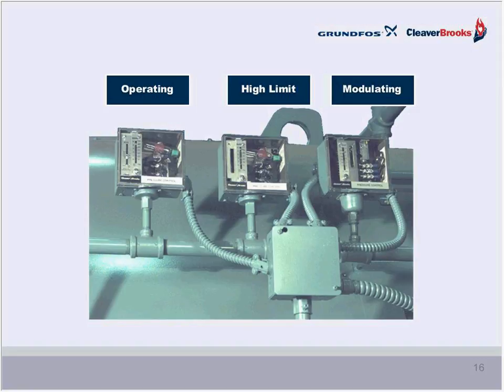And those controls I'm referring to start right here with the operating control, which turns the burner on when the load demands it and shuts it off when the load is satisfied. The high limit control is a manual reset device, and it shuts the burner off if the operating limit control fails. Now, the modulating control, seen there on the right, varies the burner's input based on a varying load demand, cycling from low to high fire and various points in between, depending on the burner's turn-down ratio.